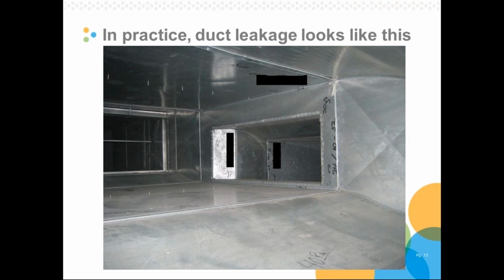This is a supply plenum that actually looks nice. The workers were very diligent. You can see there's all sorts of notes all over the inside of the ductwork that they recorded as they were putting it together. In fact, I even had to redact the name of the building because they probably did some off-site fabrication. But what we can see here is that just in this short, small supply plenum, we have tens, if not hundreds of feet of seams and joints.